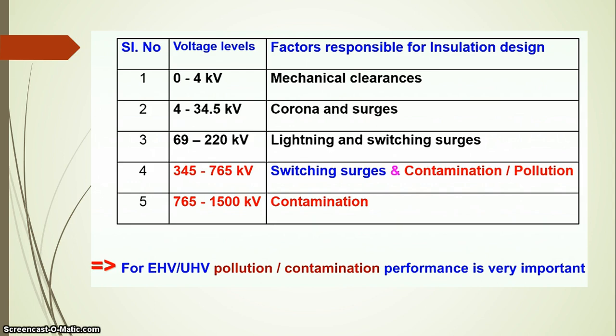The insulation design is based on various factors depending on voltage level. For 0 to 4 kV, it is based on mechanical clearances. For 4 to 34.5 kV, the governing factors are corona and surge. For 69 kV to 220 kV, lightning and switching surges are very important, so insulation design must be based on switching surge and lightning surge, and insulators must be tested for both.